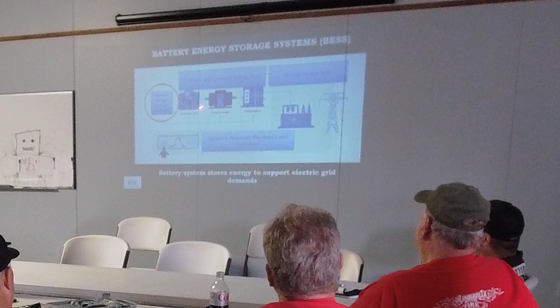Battery storage is DC voltage, just like the flashlight batteries in my kitchen drawer, direct current. But that's not what I'm plugged into in the wall outlet, right? That's AC, alternating current. So the battery stores electrochemical energy and it outputs in DC. That DC then gets converted in the inverter to AC. And from there, it gets stepped up, typically to 34,500 volts of AC, which is our common collection circuit for any generation source. Sent through some control switchgear, and then over into the actual substation bay, where it's stepped up with another transformer again to match whatever the voltage level is out on the transmission line.